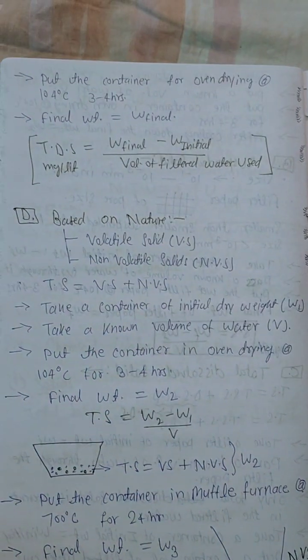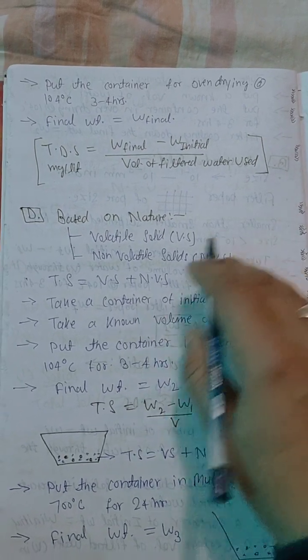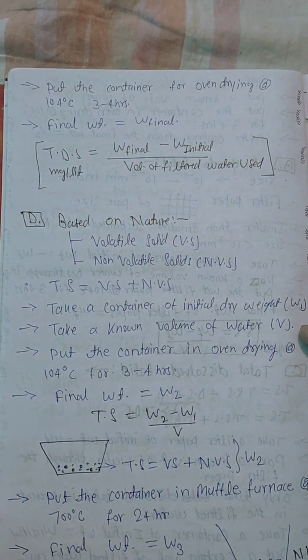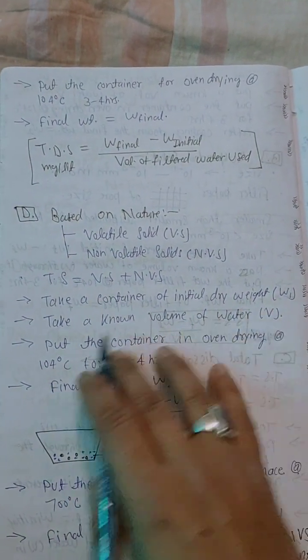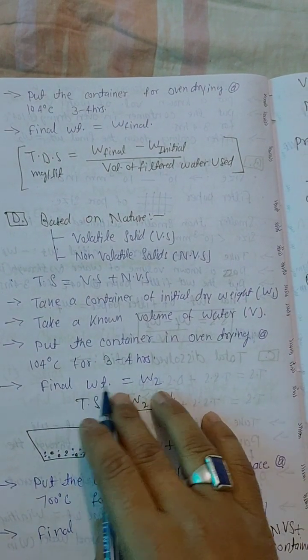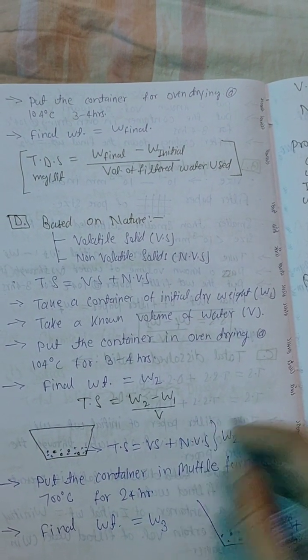Based on nature, solids are classified as: volatile solids (VS) and non-volatile solids (NVS). Total solid equals volatile solid plus non-volatile solid. To measure: take a container of initial dry weight W1, add a known volume of water V, and place in an oven dry method at 104 degrees Celsius for 3 to 4 hours. Final weight equals W2. Total solid equals (W2 minus W1) divided by V.